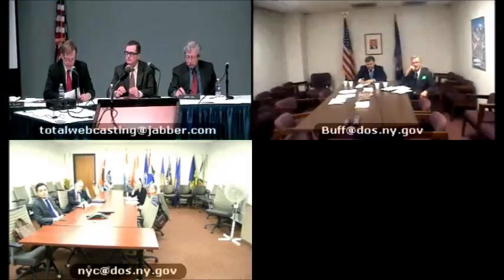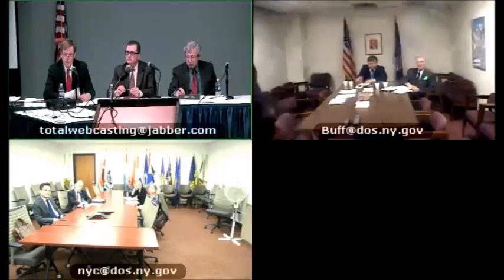I'm going to go over some of the changes that we recommended. There's basically 5 minor changes. The first one is we've changed the text to not require carbon monoxide detection in a commercial building when the building is not occupied, carbon monoxide sources are removed or disabled, each exterior opening is secured from entry by unauthorized individuals, and no attached garage is in use and is secured from use.